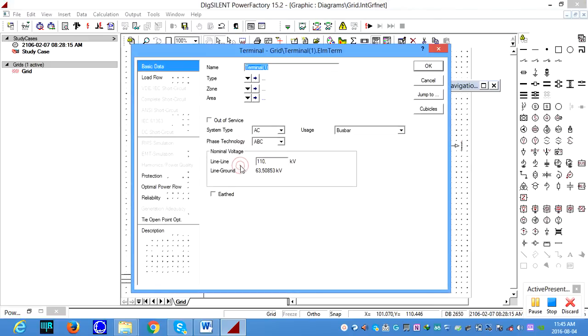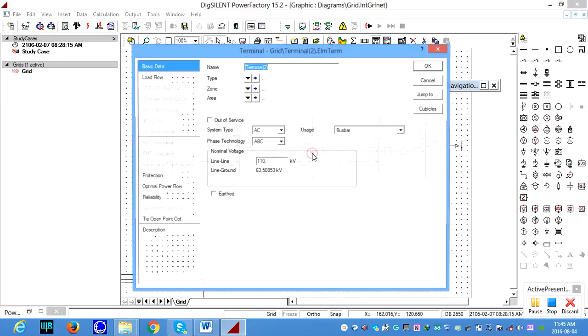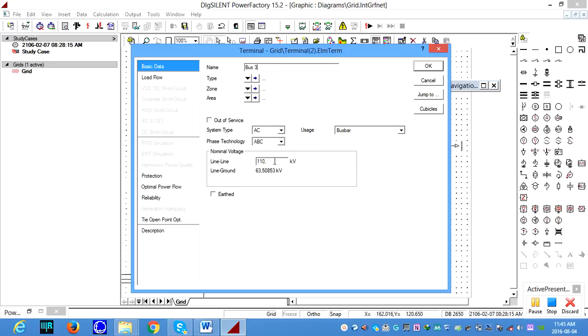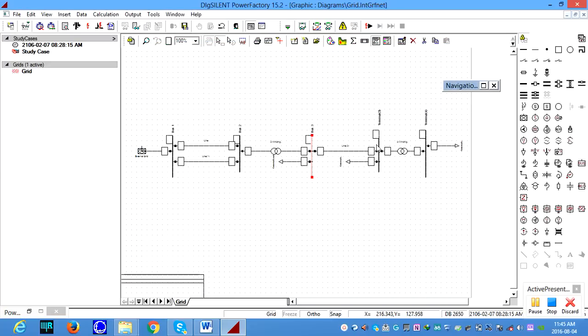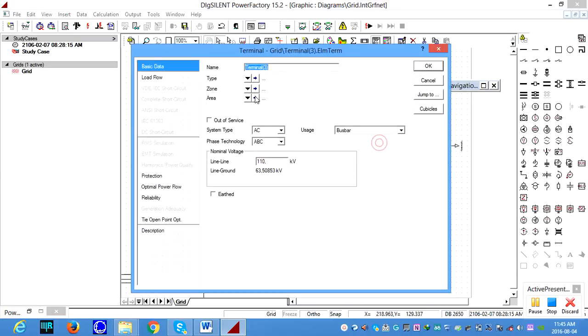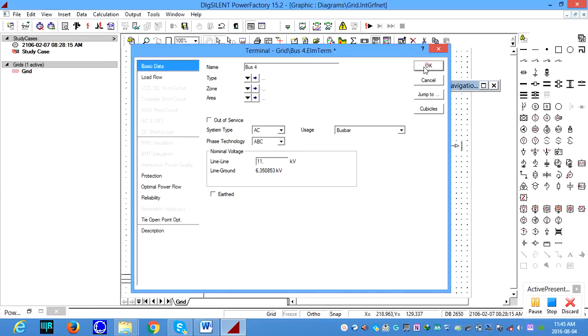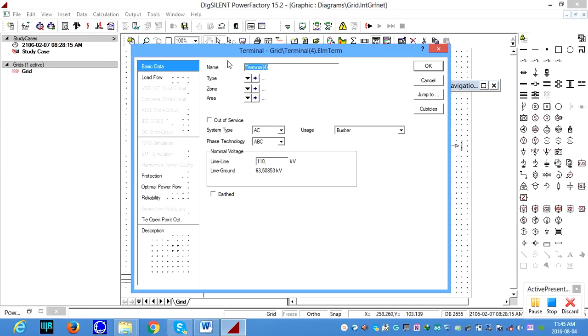and bus 2, that is also 33 kV, that AC, and the phase technology is ABC. Bus 3, that's the same way what we did, but your bus 3 is supposed to be 11 kV. Bus 4, this is also supposed to be 11 kV, and your last bus, bus 5, this is again step down to 400 volt.